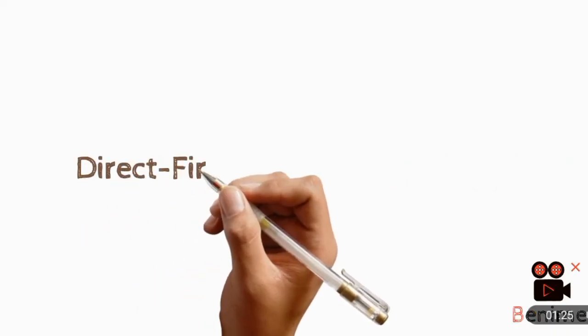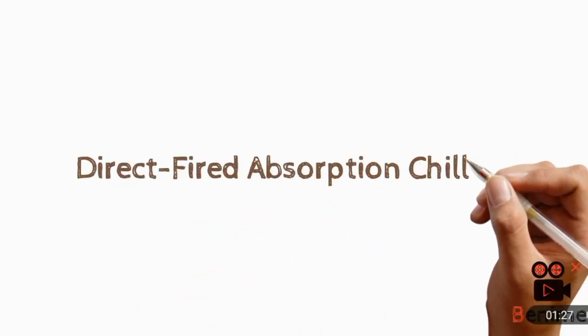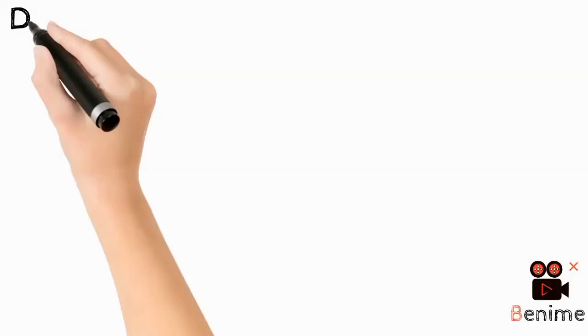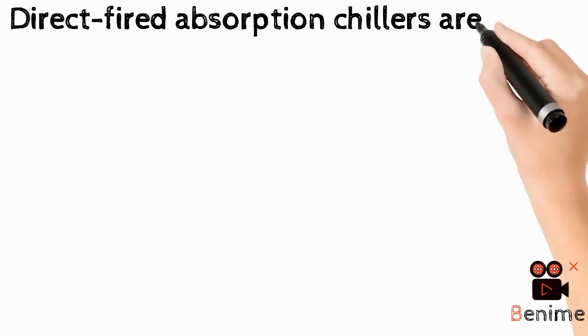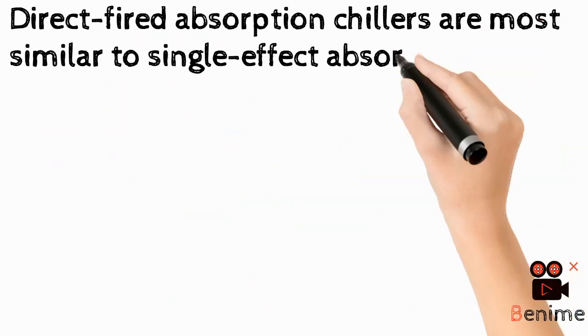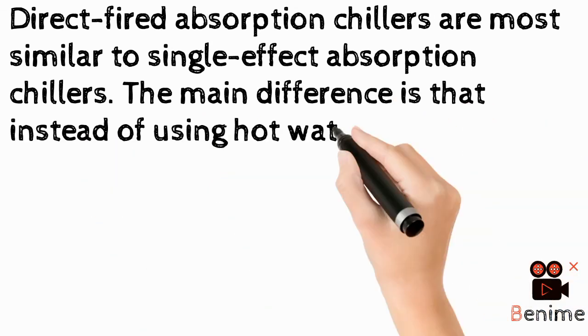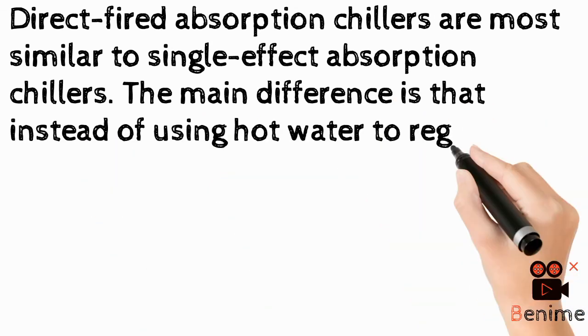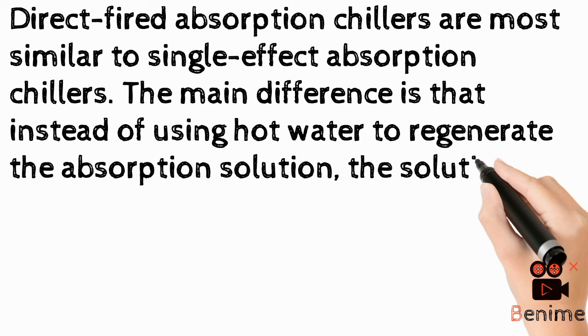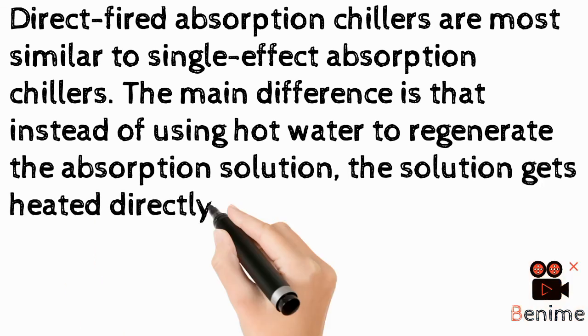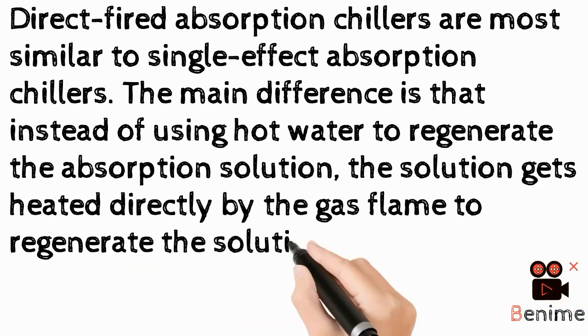The heat in the condenser is absorbed by cooling water. The last type is the Direct Fire Absorption Chiller. Direct Fire Absorption Chillers are most similar to the Single Effect Chiller, but the main difference is that instead of using hot water to regenerate the absorbent solution, the solution is heated directly by a gas flame to regenerate the solution and the refrigerant.